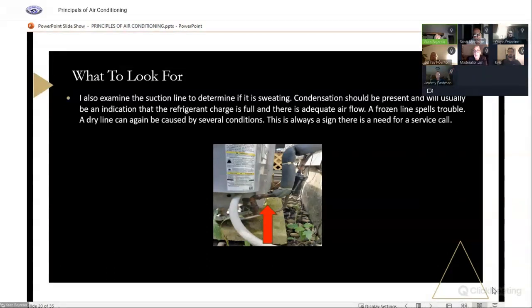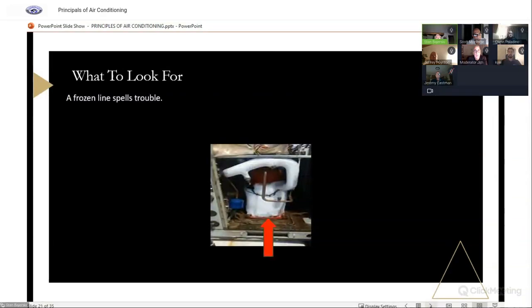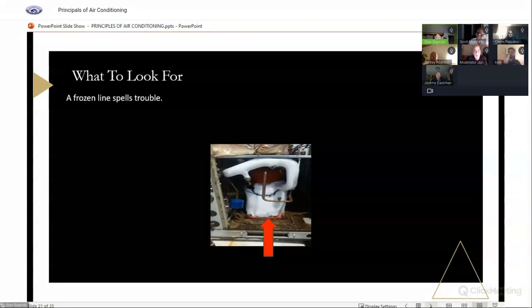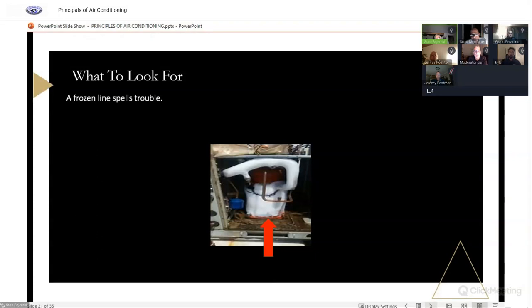However, this next one's a no-brainer. That's a problem. We've probably got big time air blockage, but again, you don't want to diagnose that. I would shut that unit off right away. That thing's slugging liquid and surprising if it's actually running, because the compressor can't compress liquid. Normally, if you see that, you're going to hear this high-pitched ticking sound because there's liquid going through those pistons and valves. And it's definitely damaging the compressor if it doesn't cause it to fail at some point. So you got to shut it down, let all that defrost, and have somebody come out and look at it.